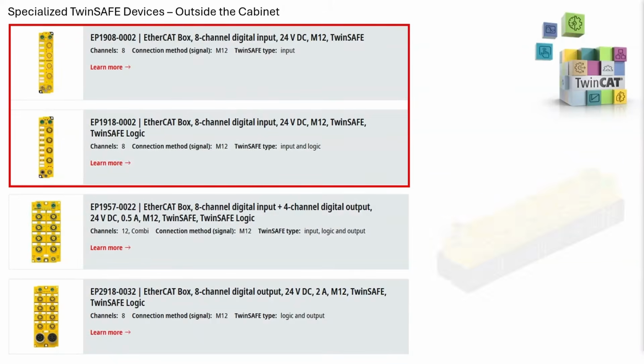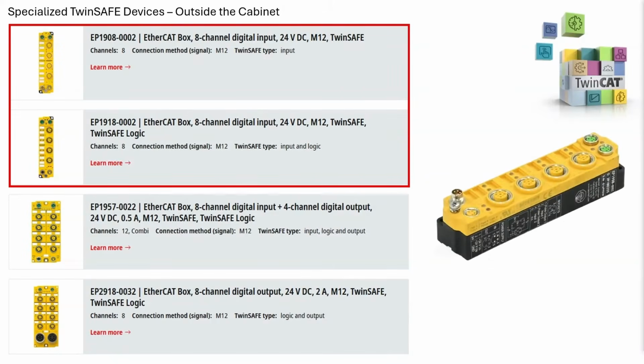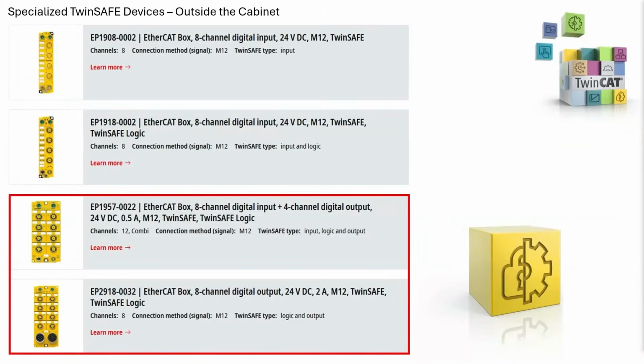The EP1908 and EP1918 are Beckhoff's IP67 TwinSAFE digital input modules designed for collecting safety-related signals directly in the field. Both modules provide 8 safe inputs for devices such as e-stops, guard switches, enabling switches, and light curtains, all communicating over FSoE. The EP1918 adds TwinSAFE logic functionality directly on the module, thus it can act as a safety controller similar to the EL6910 terminal.